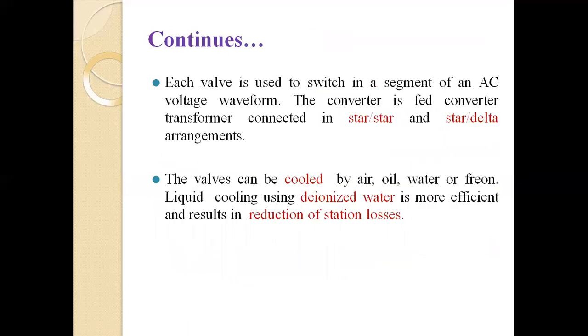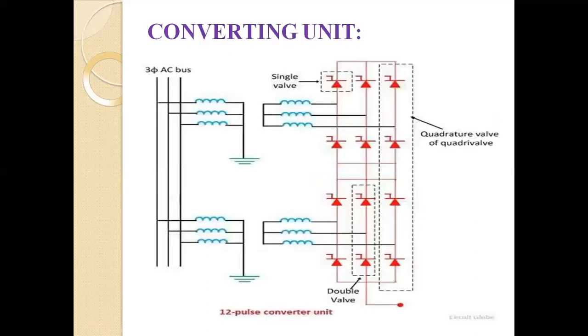Each valve is used to switch in a segment of an AC voltage waveform. The converter is fed by a converter transformer connected in star-star or star-delta arrangement. The valves can be cooled by air, oil, water, or freon. Liquid cooling using deionized water is more efficient and results in reduction of the station losses. This is the converter unit.